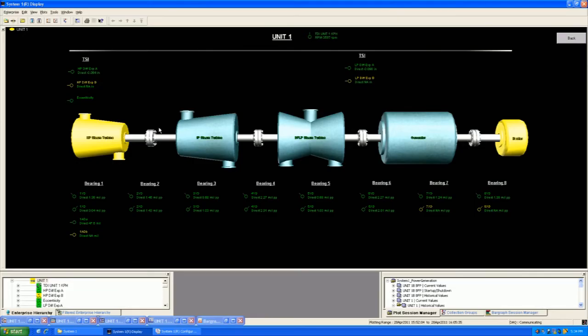So quickly, you have a nice neat look to the unit. You have the bearings labeled, and you have a quick look over the values here, and we see that there's no values over 3 mils peak to peak, which is running pretty smooth. We see that there is a couple of units in first level alarm that's indicated by the yellow, and we might use those colors and organization to go ahead and troubleshoot what might be causing those alarms.